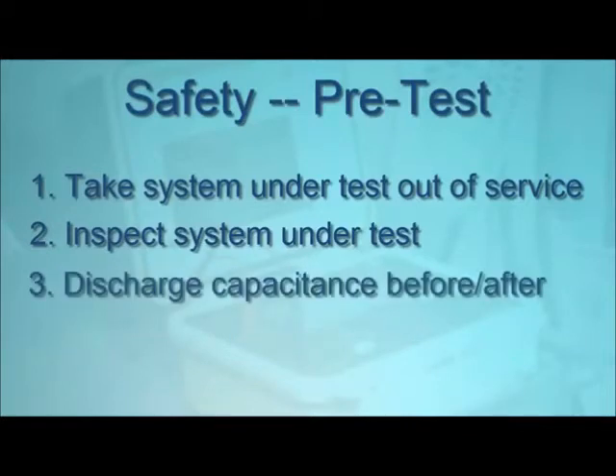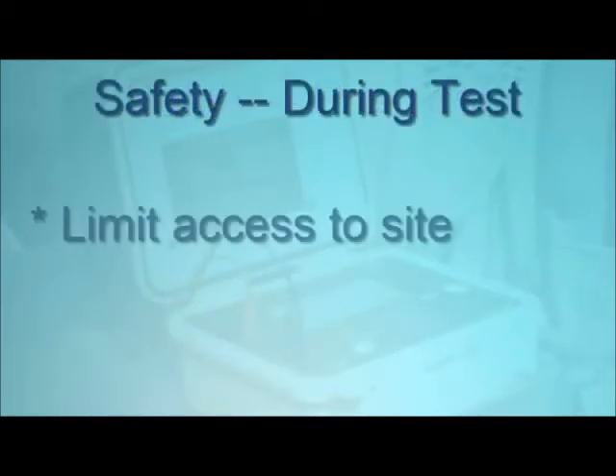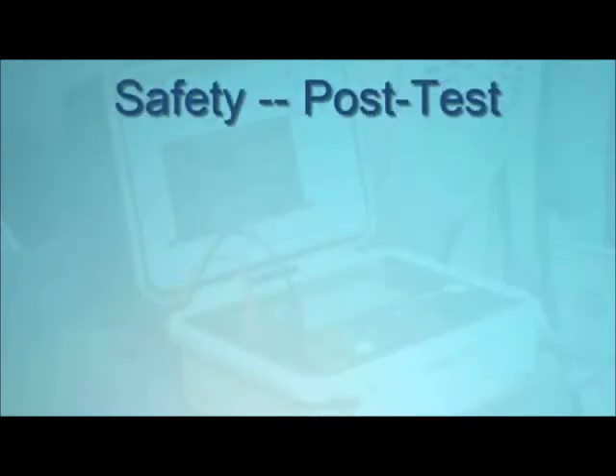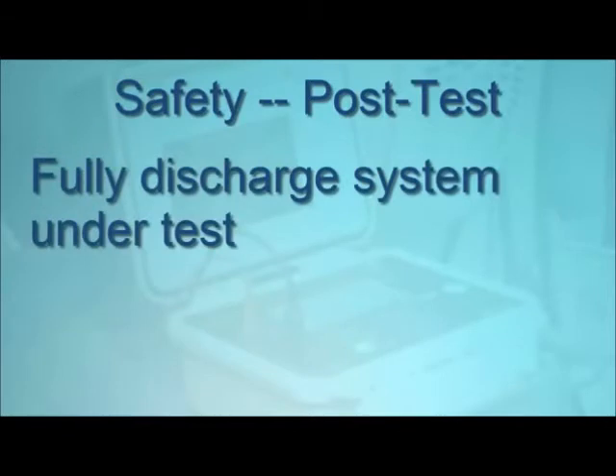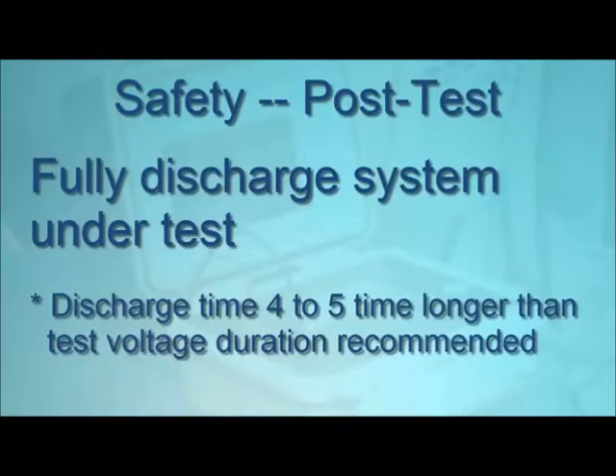Also, be sure to discharge capacitance before and after conducting an insulation resistance test. Note that AEMC megohmmeters automatically discharge capacitance when not running a test. Finally, check current leakage of switches and other connections. When performing the test, restrict personnel access to the test site, and be sure to use personal protective gear such as gloves where appropriate. After the test is complete, make sure the system under test is fully discharged. A minimum discharge time of 4 to 5 times the duration of the applied test voltage is recommended. Some insulation resistance test instruments feature a built-in circuit to ensure a safe discharge after the test.